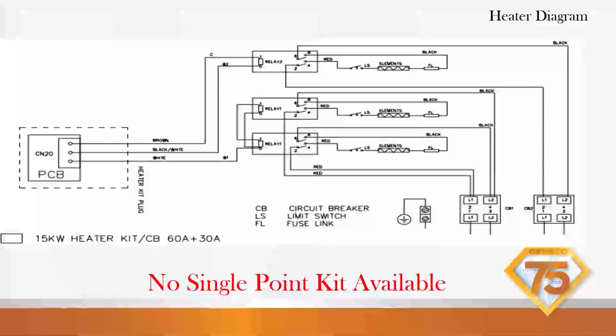And they had an electrician out there. They went through everything, right? So he's calling me up going, what in the world? We need a site visit. So I had him send me a picture of the indoor because he didn't fully understand the difference of the 60 and a 30. And I said, well, there you go. You have the 10 gauge wire going to the 60 amp circuit.